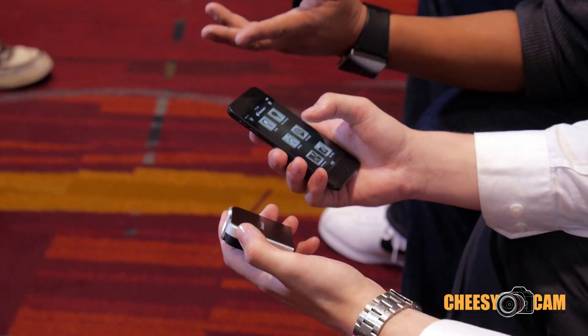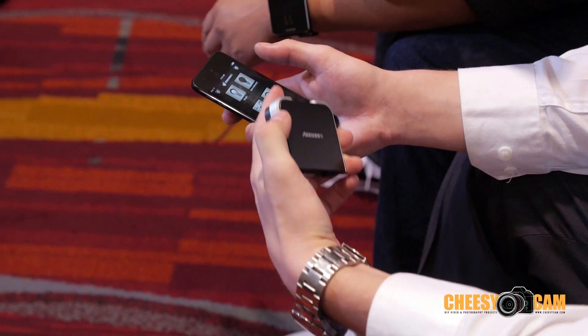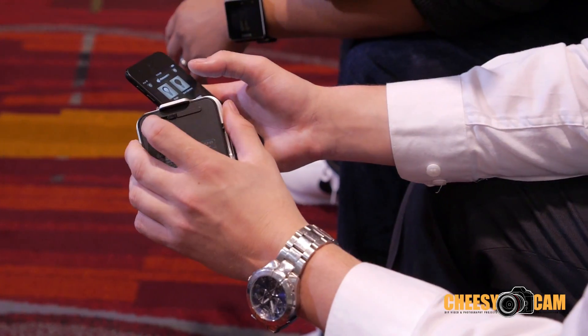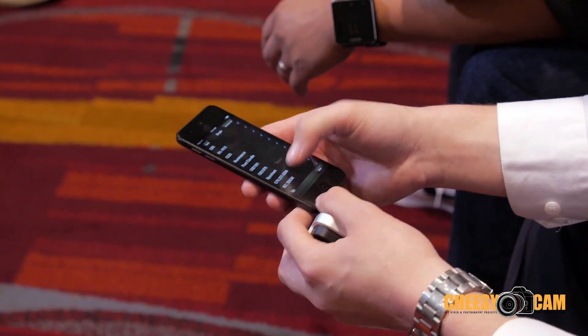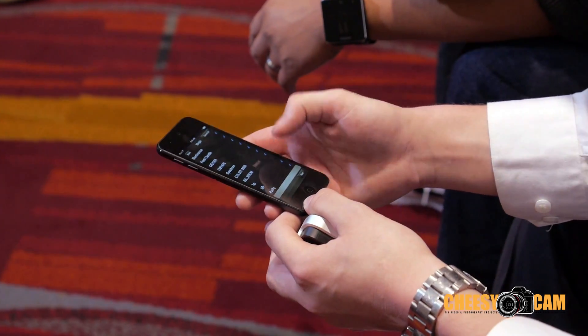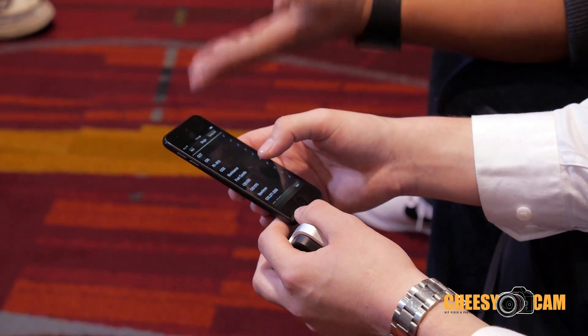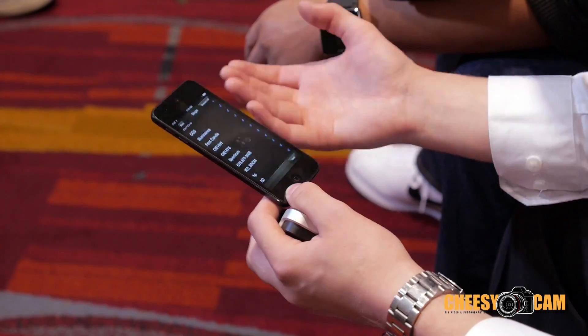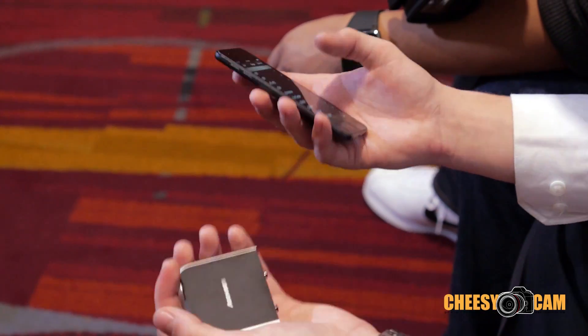This is connected via Bluetooth so you don't have to be right next to it. For a single measurement, you press the button and then select all the parameters you want. You can customize the menu — some things you don't care about, you don't have to see them. Depending on your application you can take them off, select them all, or whatever.